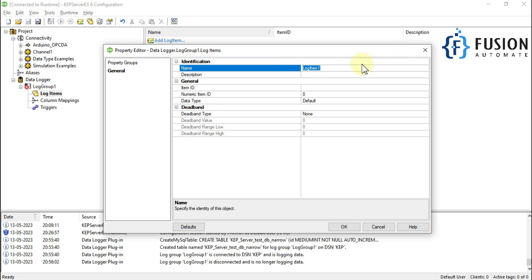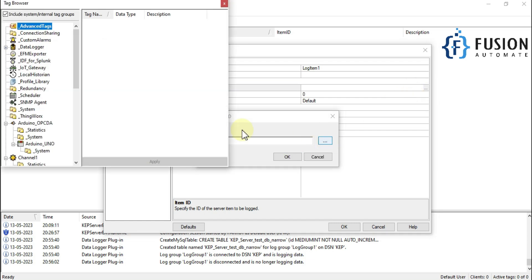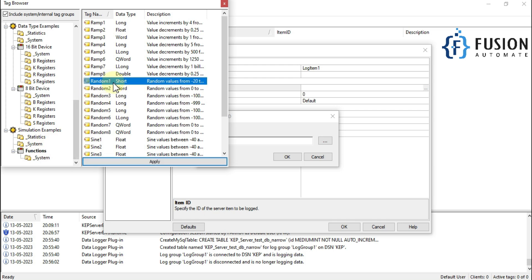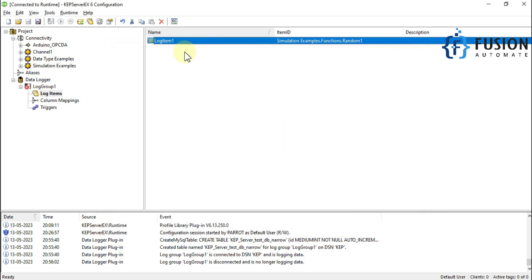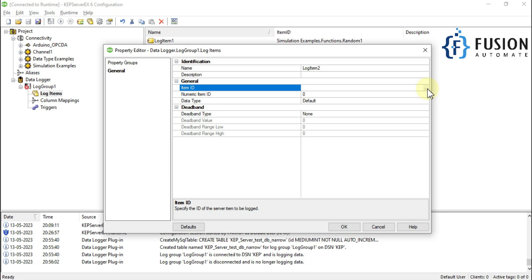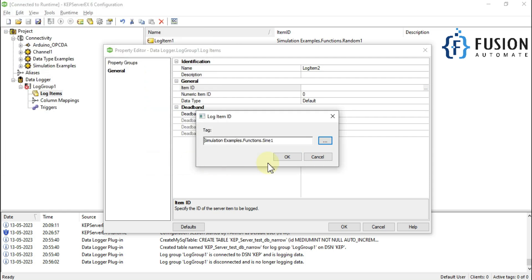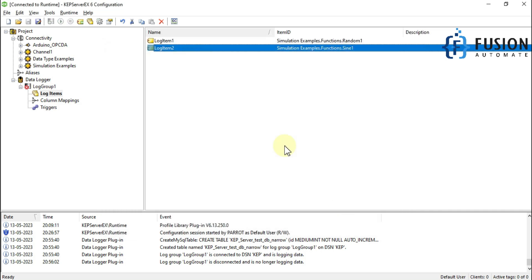Now we have to disable the log group first and then add log items — the tags we want to log. For Log Item 1, click the three-dot button for the item ID, scroll down to Simulation Example, and choose Random. Apply and OK — you can see numeric item ID 0, data type Short. For Log Item 2, click the three-dot button again, choose Sine, apply and OK — numeric ID 1, data type Float. So we have two tags: Random and Sine.